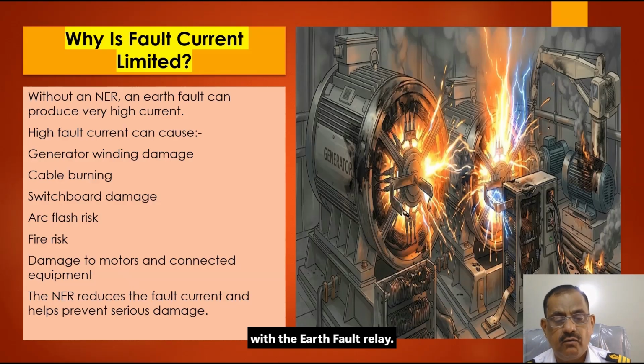The NER works together with the earth fault relay. When fault current flows through the NER, the relay detects it. Depending on the system design, the relay may give an alarm first or trip the faulty feeder. This helps isolate the faulty circuit while protecting the rest of the ship's electrical system.